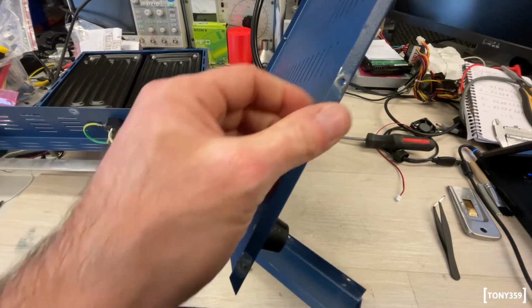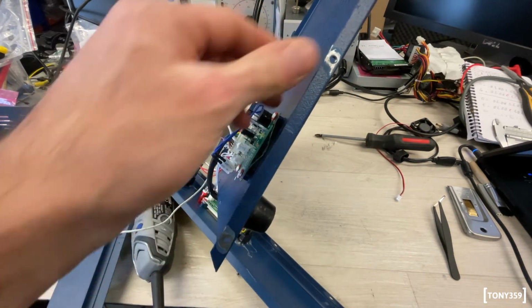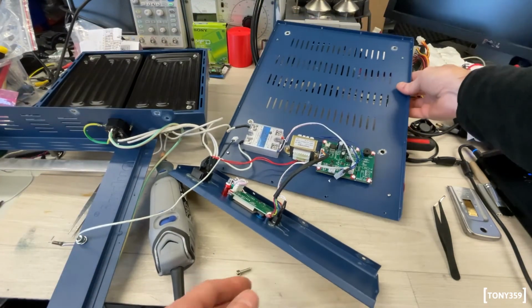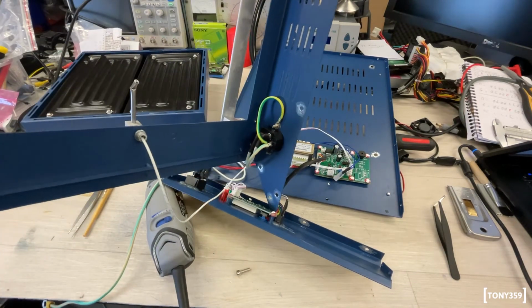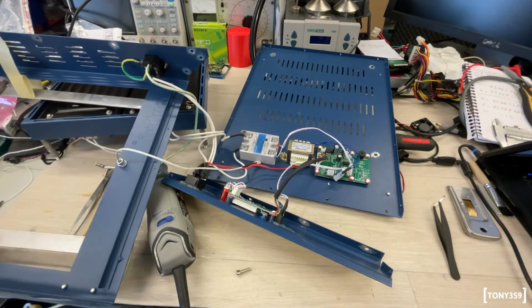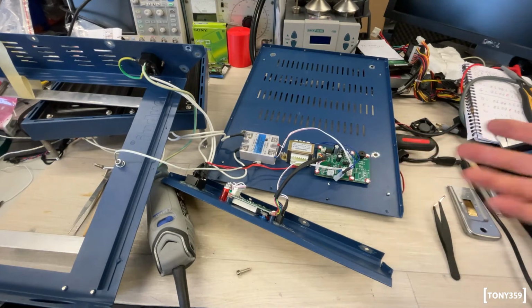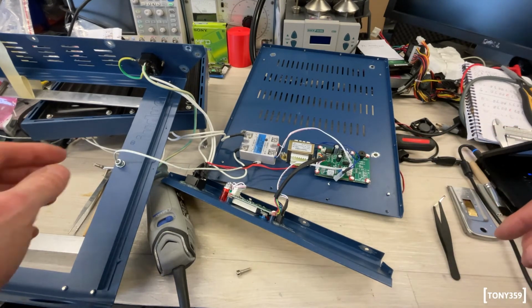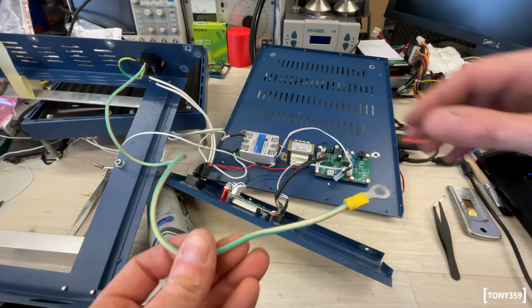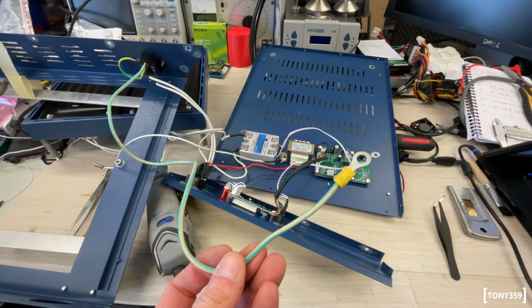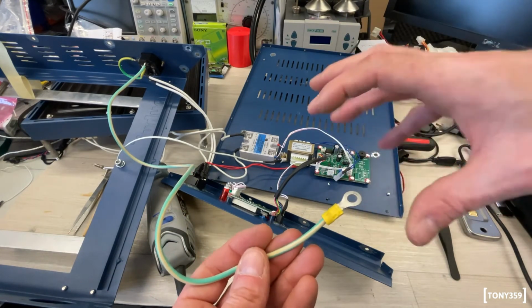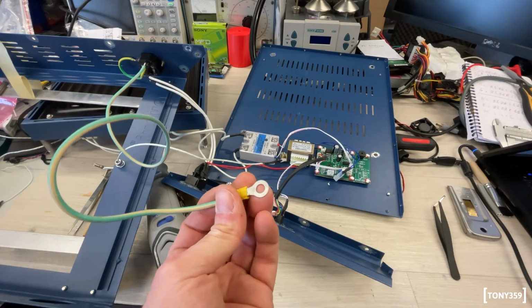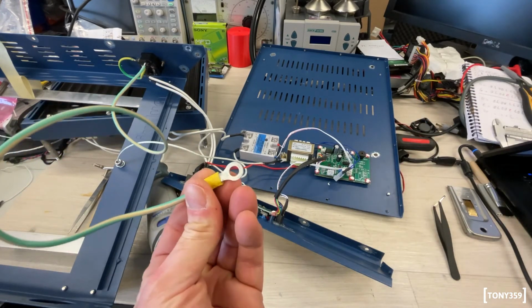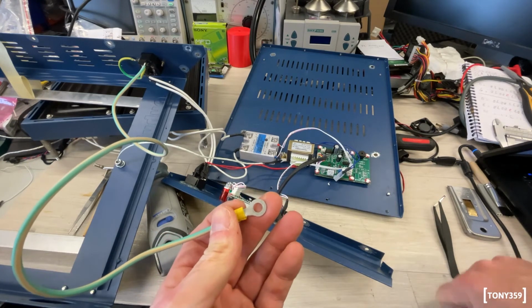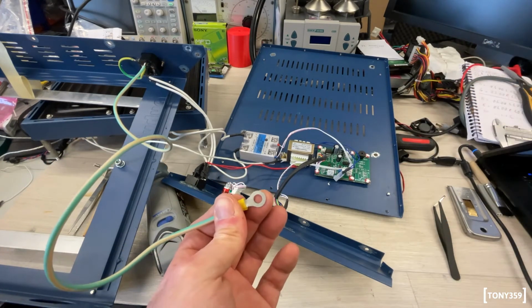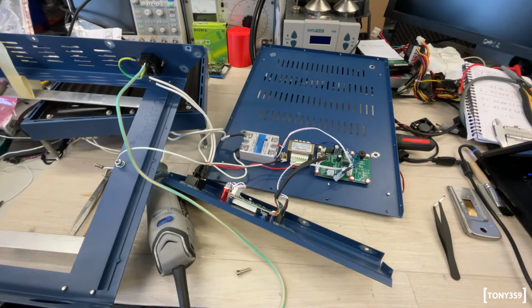So as you can see, I've scraped the paint wherever there is contact between the parts. Yes, is this overkill? Probably it is. I think ideally, when it comes to earth, you want small jumper leads like this in between parts, with a split washer to grip through the paint. I think probably this one was enough for everything. This is just an extra step to make sure, touch wood, that if something happens one day, nothing nasty happens to whoever is using the machine.